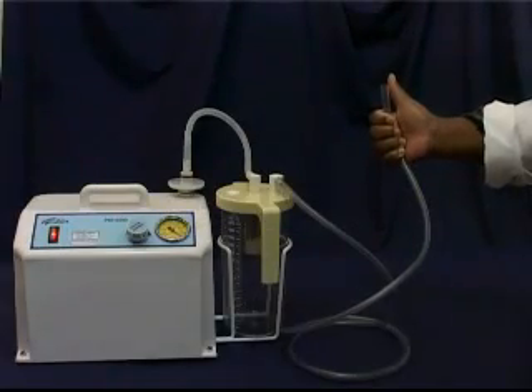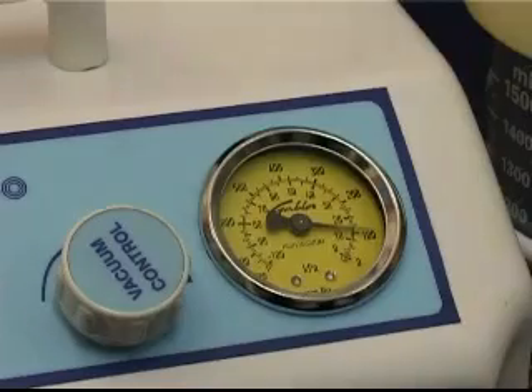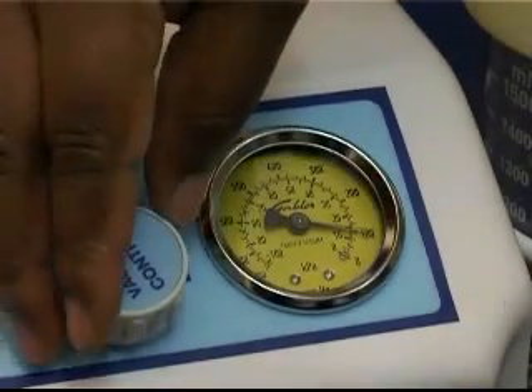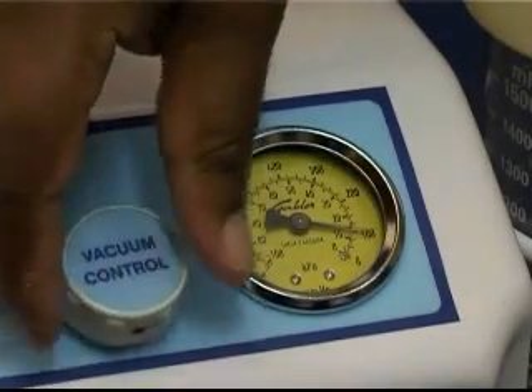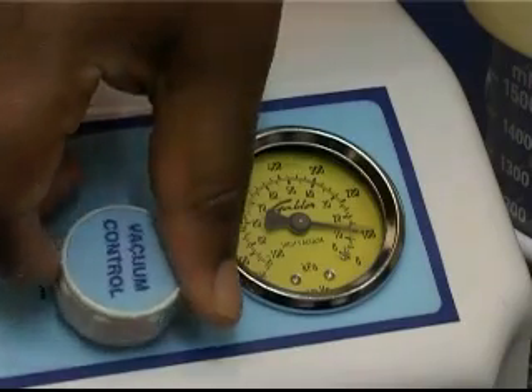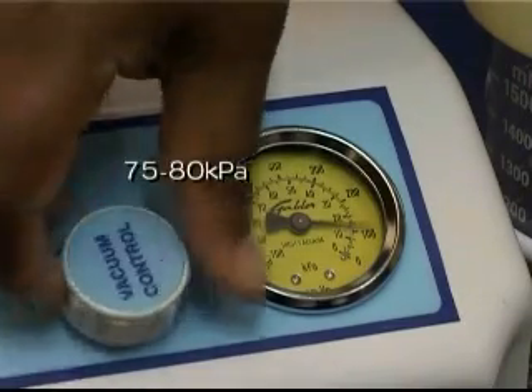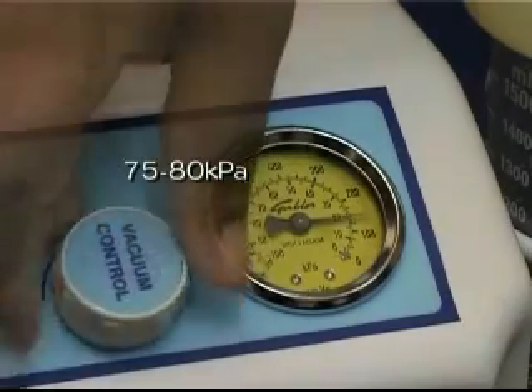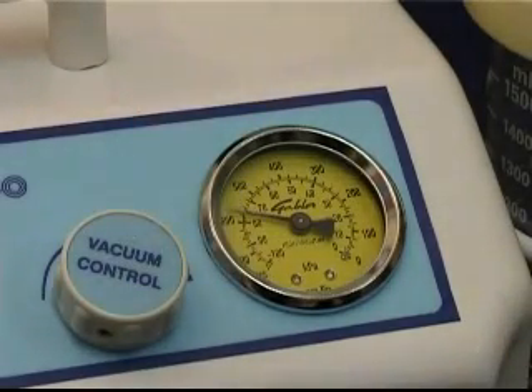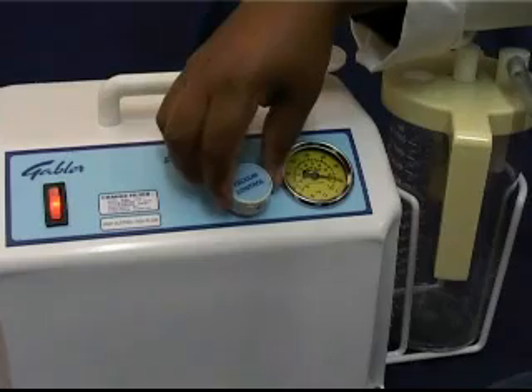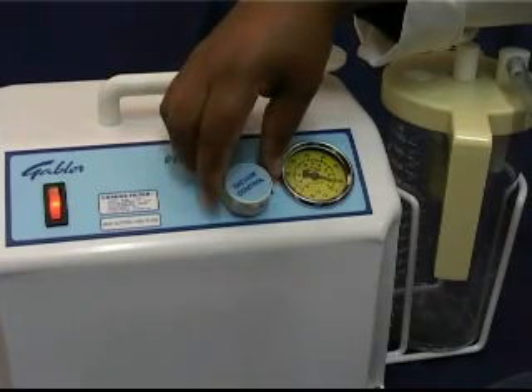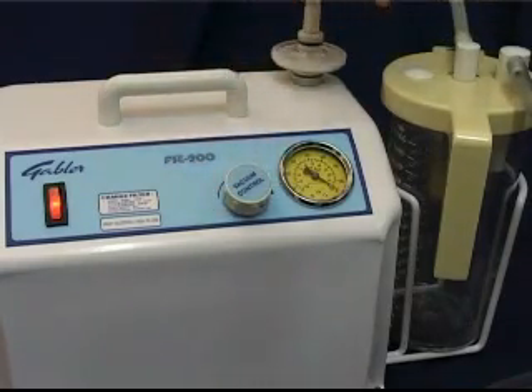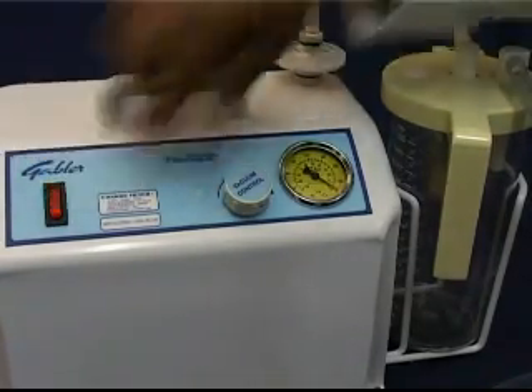Block the inlet filter connection with your thumb and slowly turn the vacuum knob towards maximum while observing the pressure gauge. The pointer should rise from a minimum to a maximum of approximately 75 to 80 kPa. Finally, turn the vacuum knob back to its minimum setting and turn off the pump.